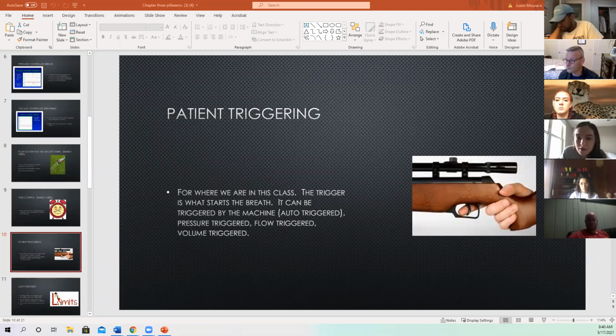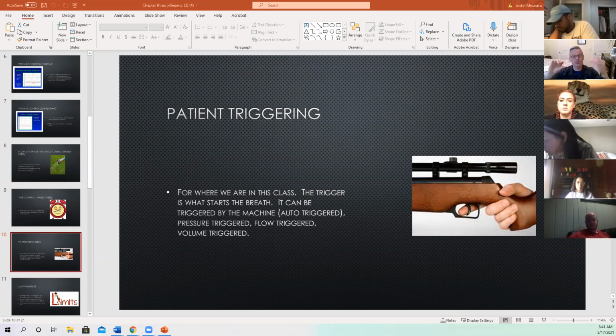The diaphragm goes down. We create a negative pressure, a negative flow when the diaphragm goes down, right? The negative pressure on the vent will suck back pressure off the system, or it'll generate a negative flow. So with flow triggering, we have flow running through that circuit. And if the patient creates a negative pressure, they'll be able to pull and generate a breath, right?